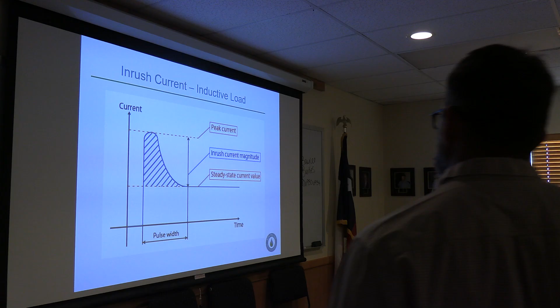It's not contributing to your system, but it's also the place where you can cause major strain on your system. That's when you can blow out contactors. That's where you can overload and trip breakers, because they're trying to protect your system from spikes. Oftentimes you can initiate a spike by turning on a motor that doesn't have some sort of starter or a controller. As you know, the electric motor doesn't have a throttle that you can lean into.